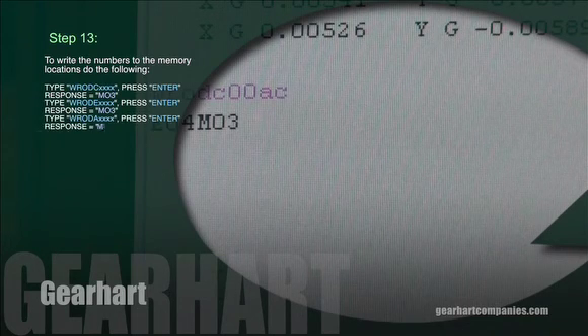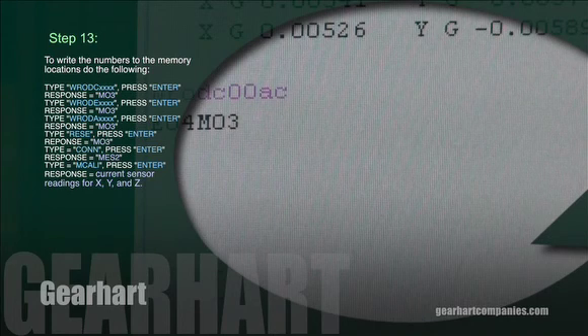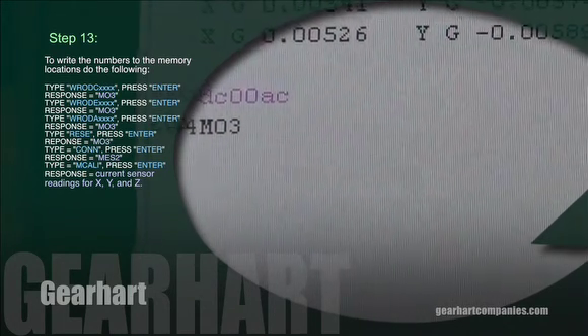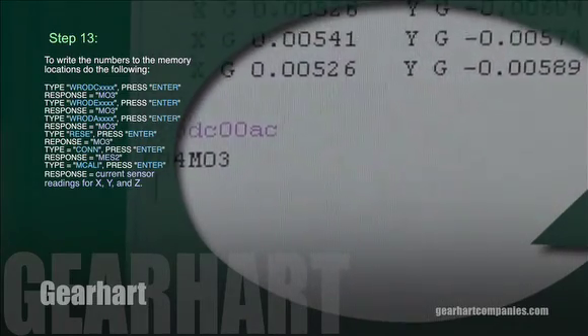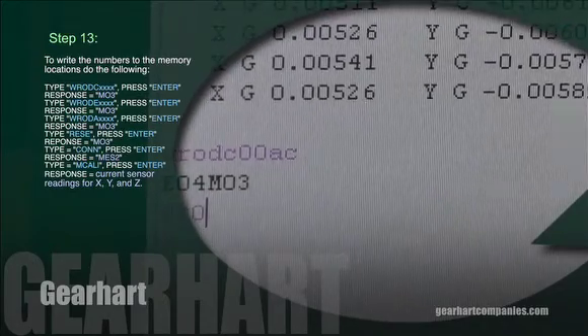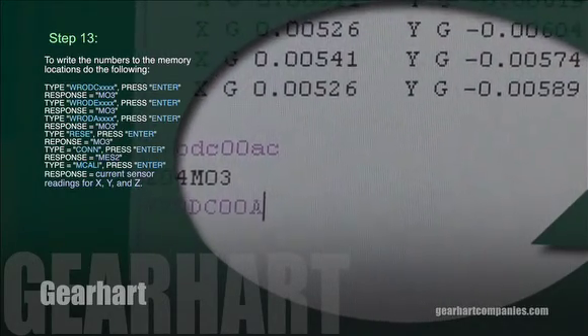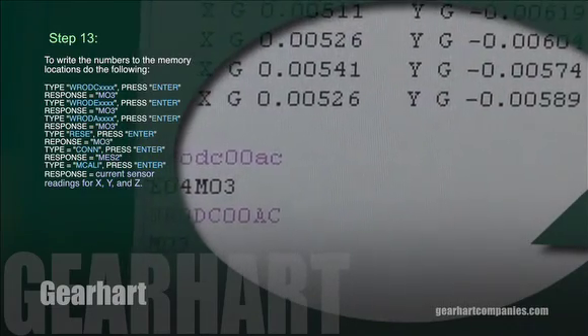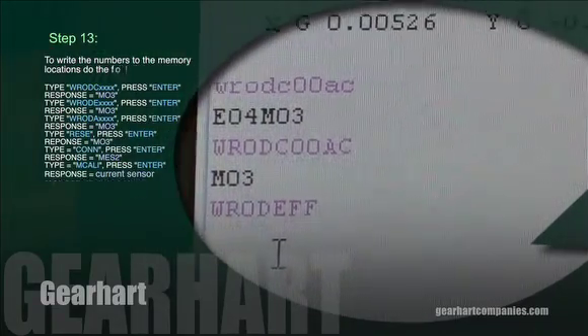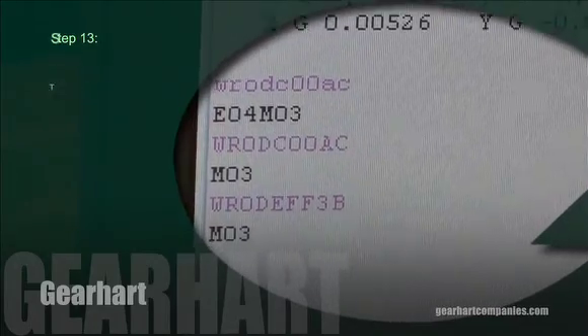Type WRODC, then the hexadecimal number from step 10 above, getting the response M03. Then type WRODE, then the hexadecimal number from step 11, getting the response again M03. Then type WRODA, then the hexadecimal number from step 12, getting again the response M03. Then type RESE, then press enter, getting the same response M03. Then type CONN, getting the response MES2. Then type MCALI, press enter, and then getting the response of the current sensor readings for X, Y, and Z.